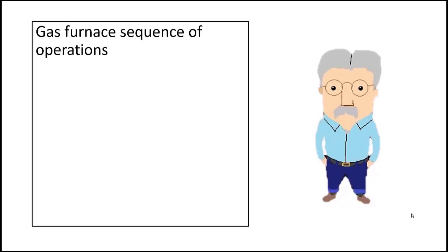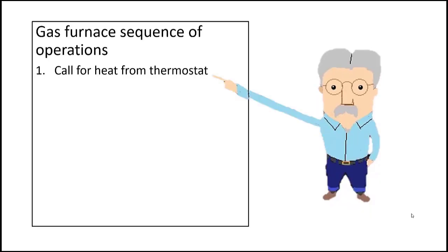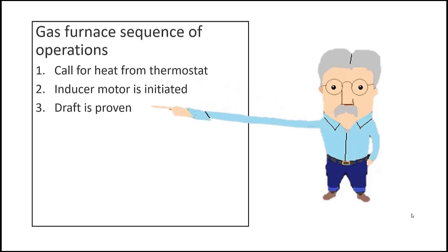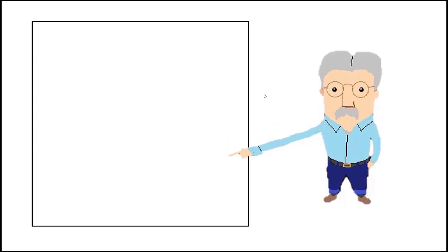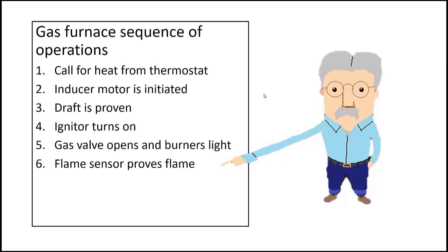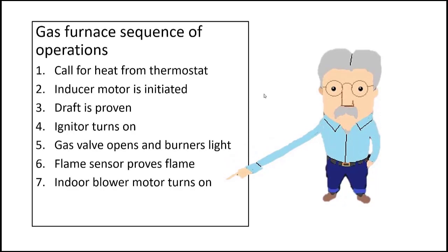So let's go over that basic sequence of operation. The first is a call for heat from the thermostat. That starts all action. The draft inducer motor starts. Then draft is proven. The igniter turns on, and that could be a hot surface igniter or a pilot. The gas valve opens and the burners light. But then we have to prove there's flame. The indoor blower turns on. And we have a happy customer. So that's the basic sequence of operation.